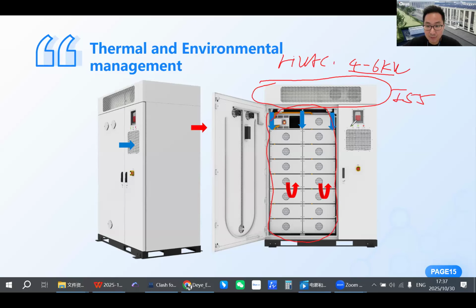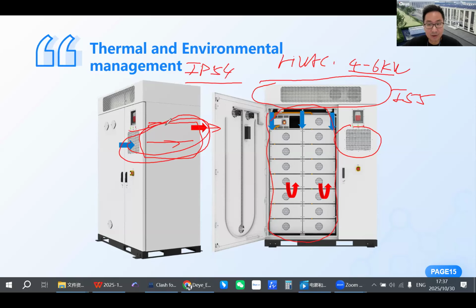IP55. But for our PCS, if you remember previously, the PCS is somewhere down there. It's forced ventilation. There will be a huge exhaust fan pulling cold air from the front and pushing the hot exhaust out from the back. The PCS and MPPT modules themselves are actually IP65. So we make the electric compartment for the PCS IP54 only, because they don't really need IP55. The PCS is watertight, so there's no point. That's why you can see on the spec sheet the overall rating is IP54, because the rating takes the lowest number.